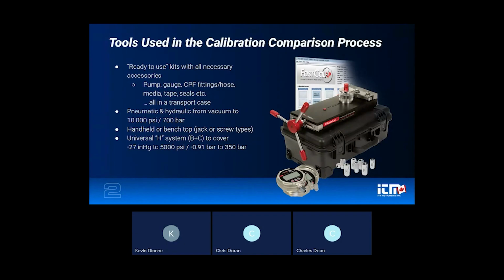These systems are available as complete kits, which simplifies your setup by ensuring compatible components. From an application standpoint, once again, I'm using the same instruments here, but the XP3i is compatible with these AMETEK kits. It gives you your reference instrument, your pump and all of the fittings in one package. Whether calibration is being performed with handheld pumps in the field or in a laboratory, it's a good setup for you to use. This approach reinforces the separation between pressure generation and measurement. That's going to be key going forward for us.